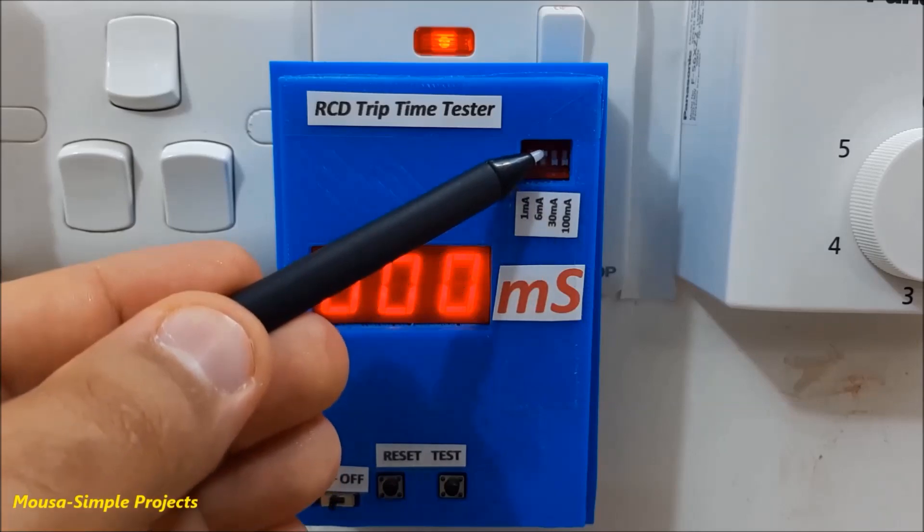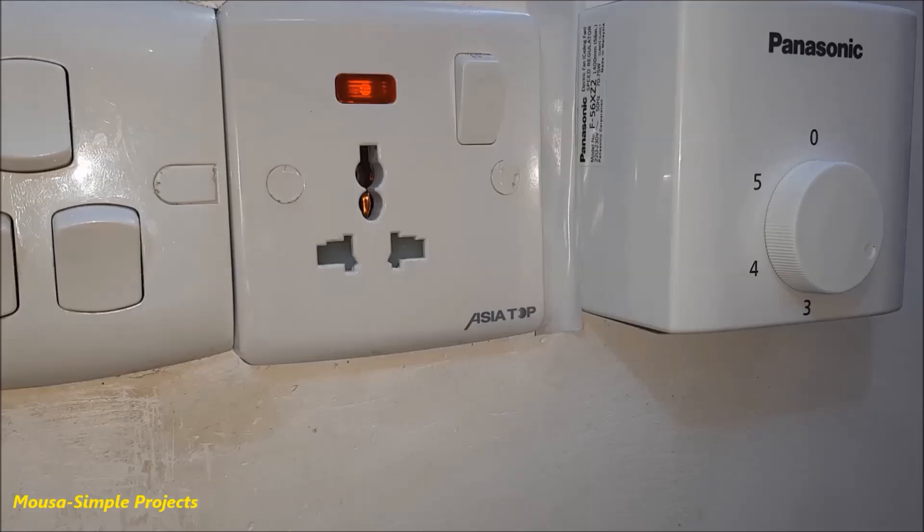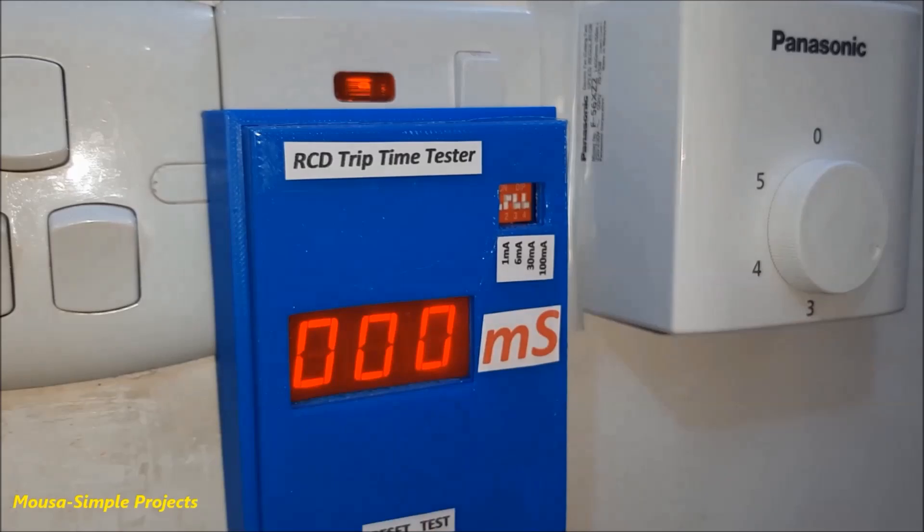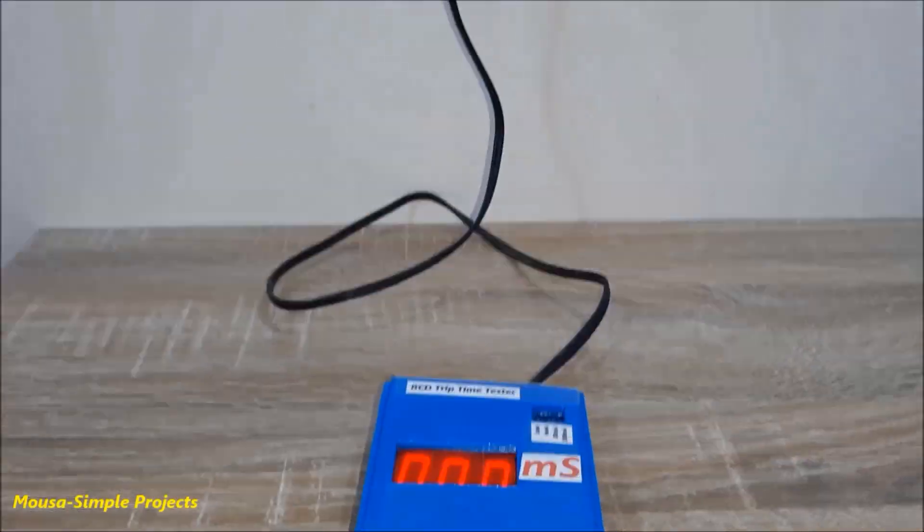With 6 mA of leakage current, the RCD does not trip. Instead of plugging the enclosure to the socket, we can use a cord wire.